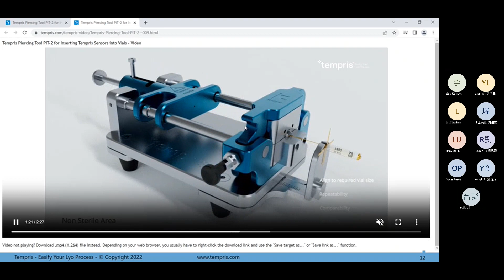This is not a sterile area. We are working in an area not sterile for preparing this. As soon as everything is ready, we put it in a special holder, which could be configurable depending on the length of the sensors or stoppers, etc. It's basically a holder where we will place all the sensors. We protect the sensor antennas from the top. We cover everything with a sterile bag, a medical bag for autoclaving, and then we bring it to the autoclave.